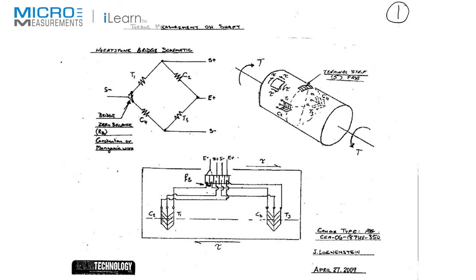So what I do is map out where I'm going to put the gauges on the shaft, in 3D, putting the direction of the strain configuration on the shaft. We are using two types of strain gauges — either a half-bridge shear gauge, where the axis of the two gauges, the line dividing the two gauges, is placed along the axis of the shaft on the surface. One also places the same gauge diametrically opposite on the other side of the shaft to create a four-gauge full Wheatstone bridge circuit for torque measurement. I've drawn the outline of the gauges on the shaft and applied strain transducer terminals between the gauges at 90 degrees, completing the Wheatstone bridge.